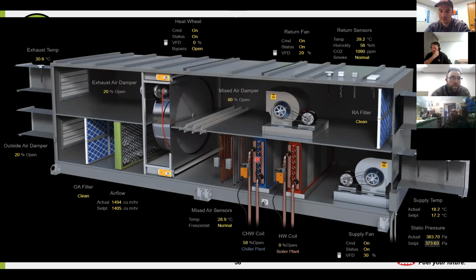And in this case, we're actually calling for cooling. We see that because our chilled water coil is 58% open, and we can see that our set point is 17.2 degrees Celsius. The actual temp is 18.2 at this time. So we need to be cooling. The air is going to pass through this chilled water coil, lose some of its heat into the water, and then be delivered to the space.